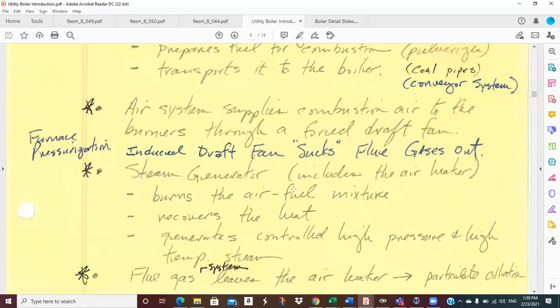And I'm not sure which one, but one of them has the induced draft fans before the, I'm sorry, not the pulverizer, the electrostatic precipitator. It's the electrostatic precipitator that takes all the fly ash out of the exhaust gas stream, all these billions and billions of small particles. Well, on half of the units, roughly, they put all those particles through that ID fan, and it just eats it to pieces. They have to rebuild those fans every 1 to 2 years. They glue ceramic plates to them. They do all kinds of stuff to keep that fly ash from eating up the ID fan.